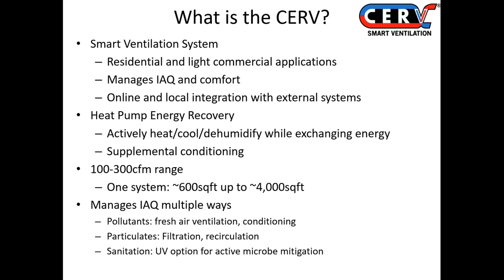The airflow range is 100 to 300 CFM. So a single system can go down to maybe 600 or so square feet and up to 4,000 square feet or so. And it manages air quality in multiple ways. Handles pollutants by fresh air ventilation, as well as conditioning, considering moisture as one of those pollutants. Particulates via filtration and recirculation, and active sanitation with UVGI to kill microbes that may be on surfaces or within the airstream.